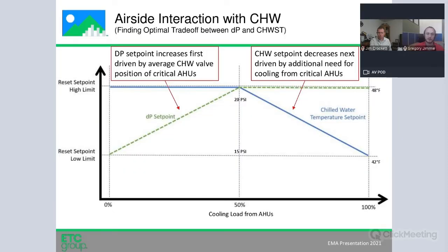Next slide here kind of gives you a little bit more of a visual on how you go about doing that. Generally speaking, like I mentioned, you want to do differential pressure first, as far as responding to the demand first with the pumping, and then secondary with the chilled water. So in this graph, you can see the beginning of what we would say is a PID loop, or a pressure control loop of cooling demand is maybe another way to think about it.